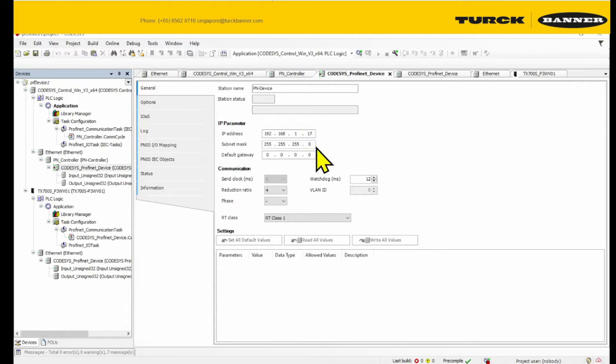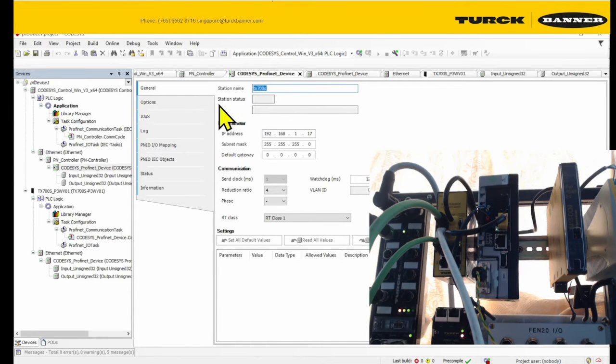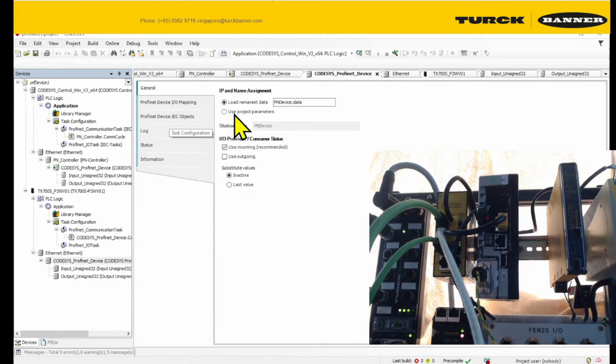Your TX700S doesn't allow IP changes due to ProfiNet. Another thing — you need to make sure that this name is the same as the name in the ProfiNet device. Go to ProfiNet parameters, change it, and save.